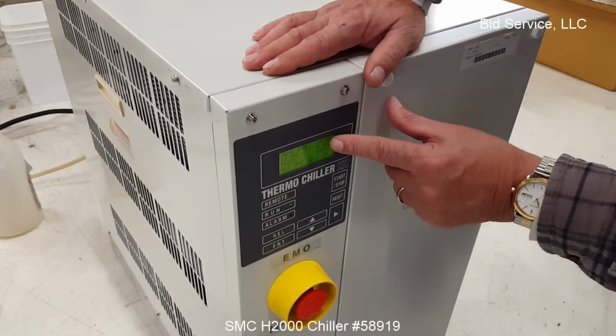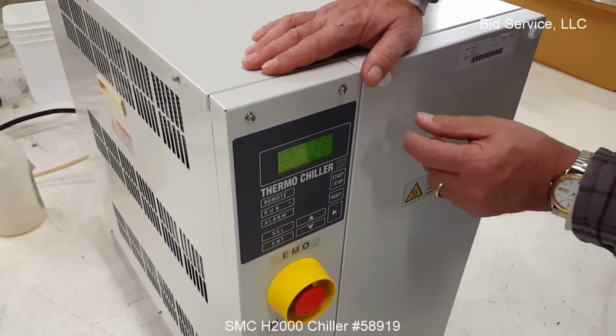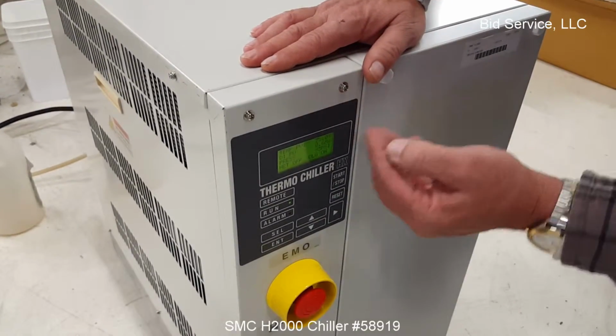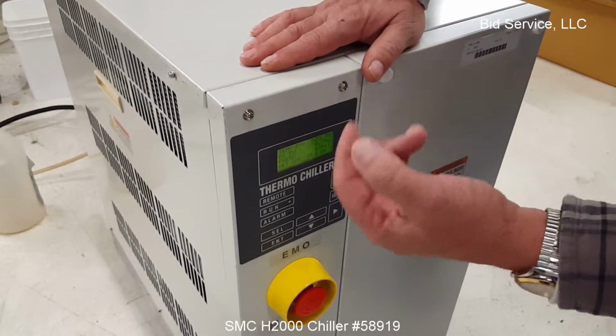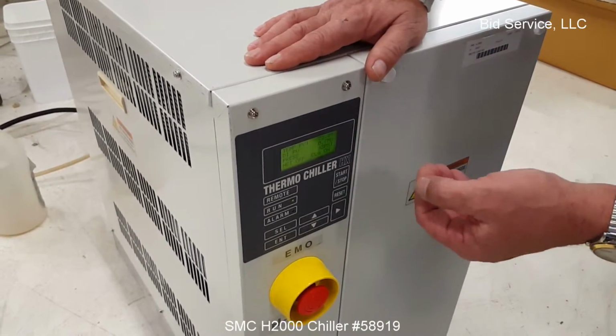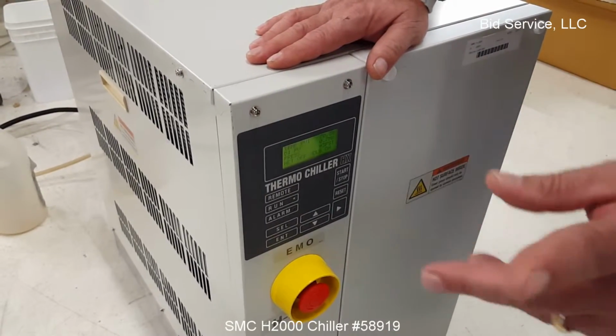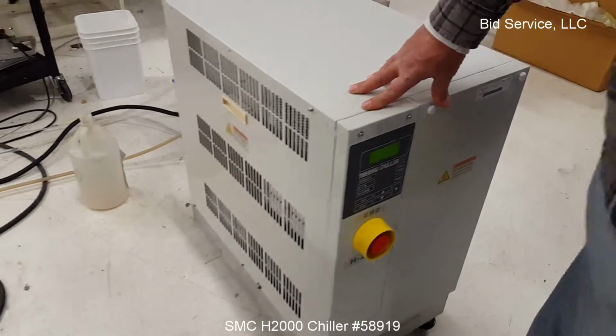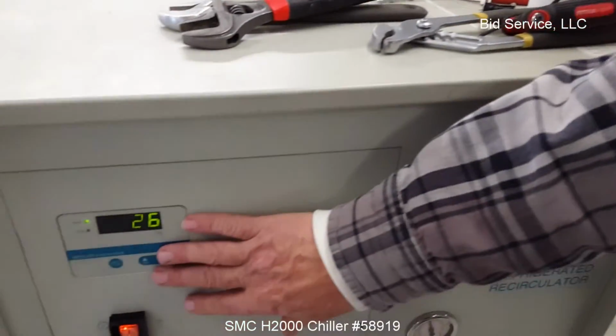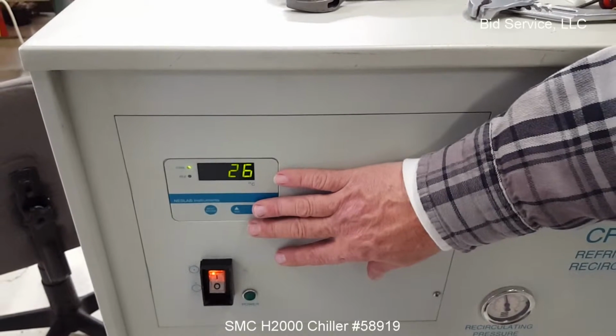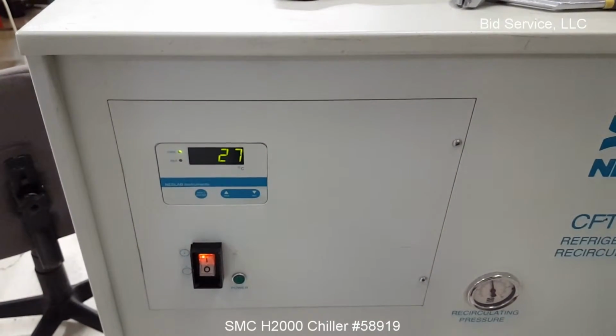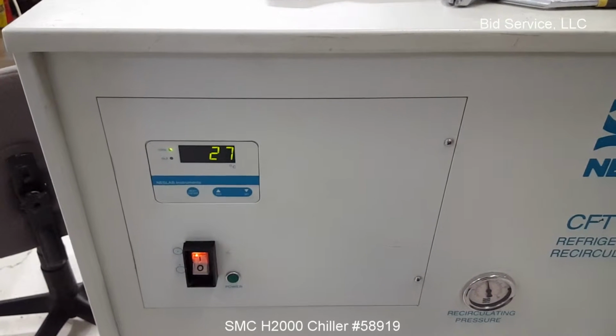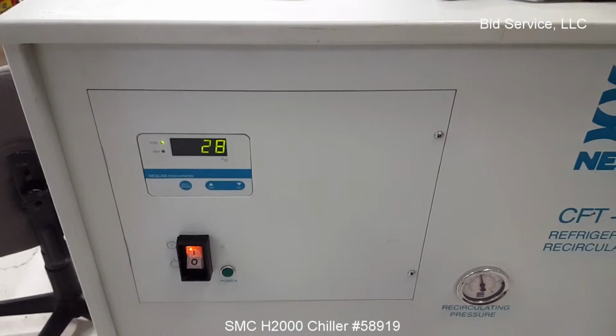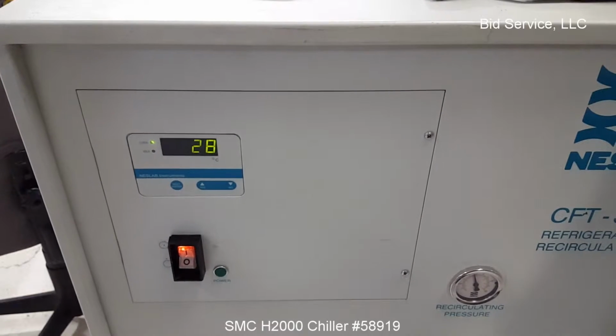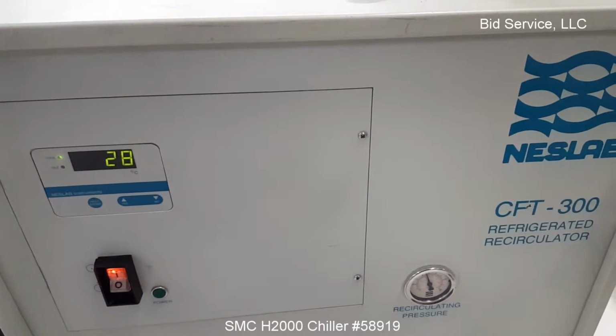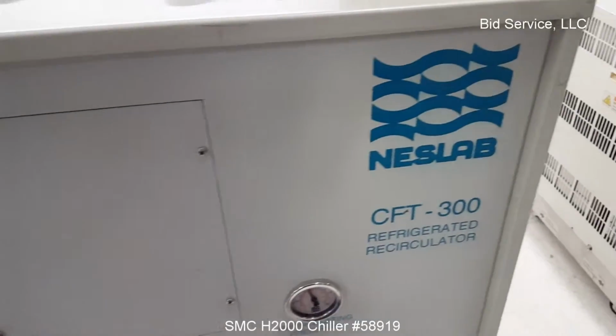And now you can see that the temperature has started to drop. Since that started to drop, it means we're pulling heat from the recirculating fluid out through the chiller. If you look at the front of the chiller reading, you can see that this temperature is rising, so the heat exchange is taking place. And when this comes down to 30, as I set it for, it would eventually start controlling at that temperature again.